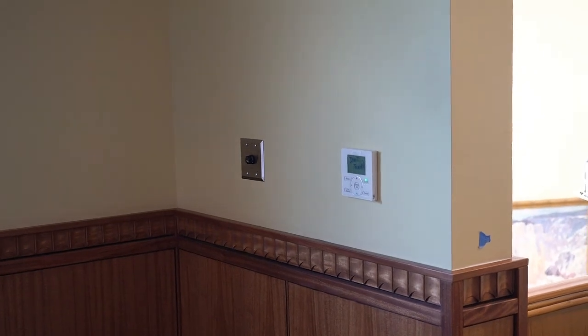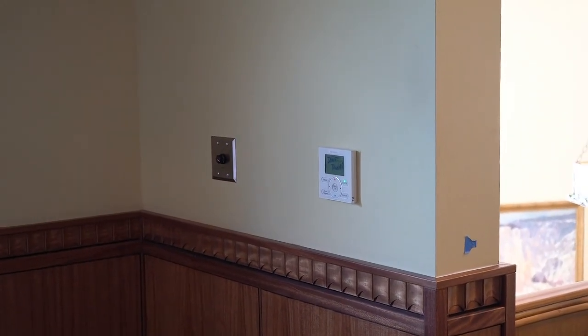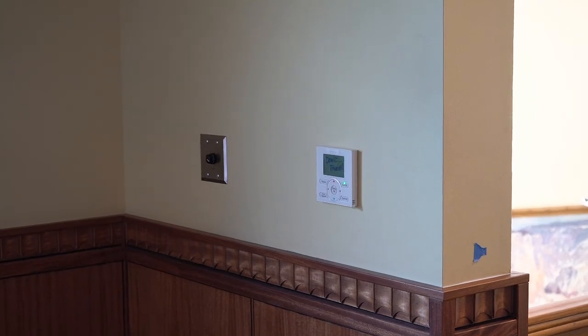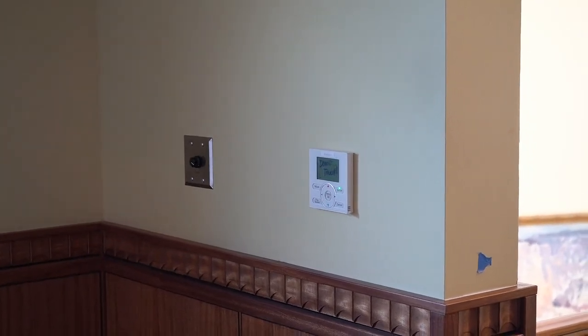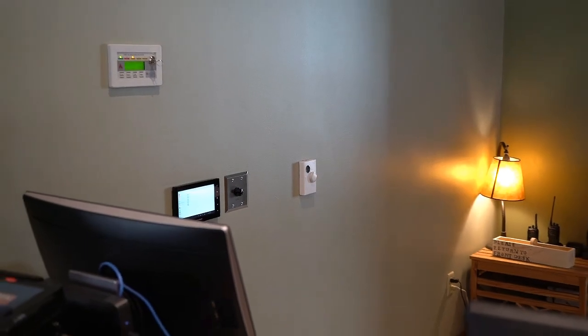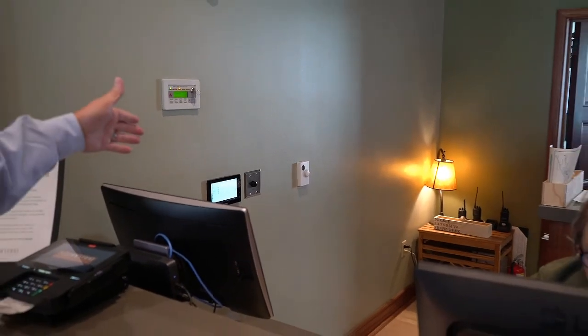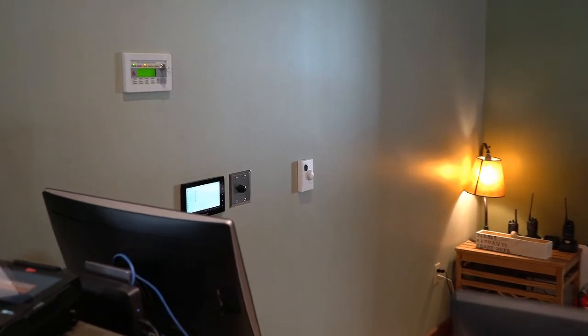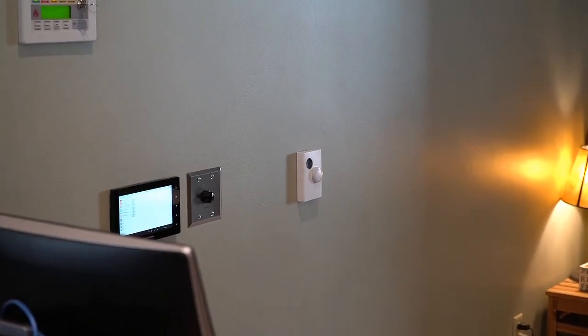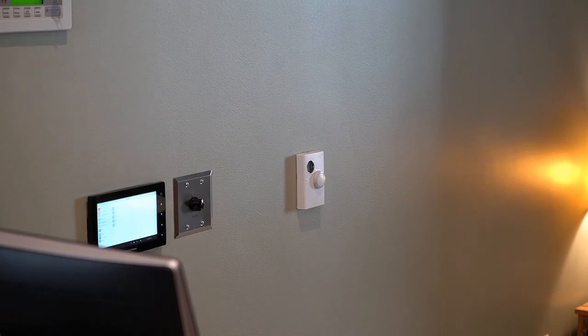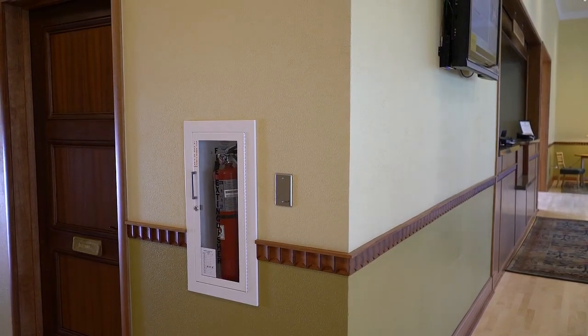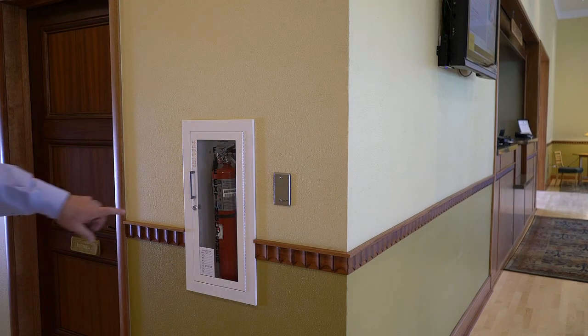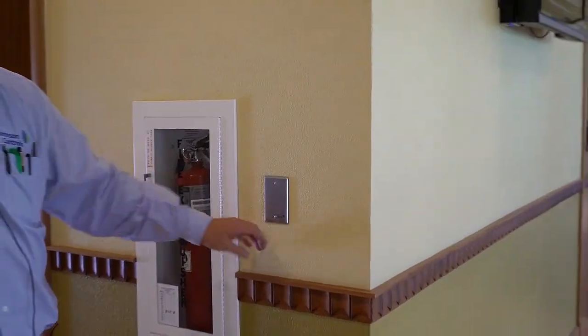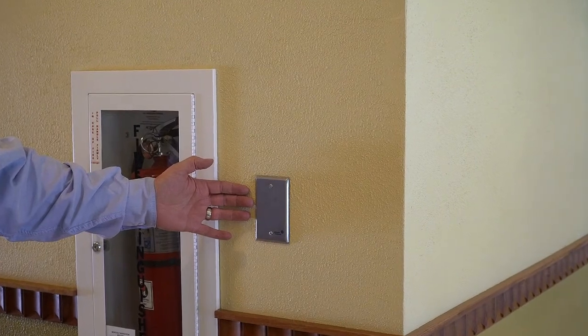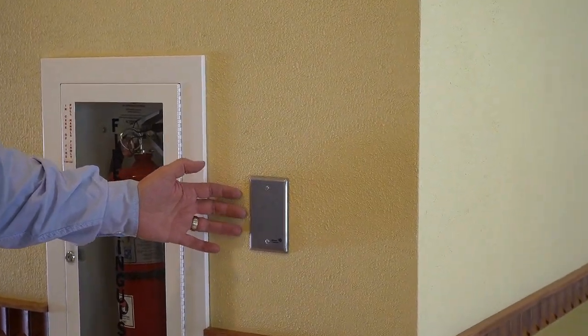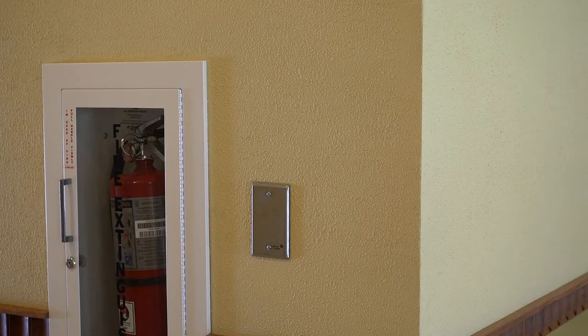Again, on second floor in the main lobby area, just coming up from the steps downstairs, we have another Daikin stat, and it just does this lobby area or hallway area. So we're in the registration area, and you'll see the temperature sensor back here on the wall. That has a dial adjustment to set the temperature. That sets the temperature for the lobby area. So that'll give us our set point. And then around the corner from the registration area, we have the stainless steel plate on the wall. It does have Johnson Controls on it. This is where we're actually sensing the temperature of the space. Okay. So this is a space temperature sensor. The other one that we just shot is how we set the set point.